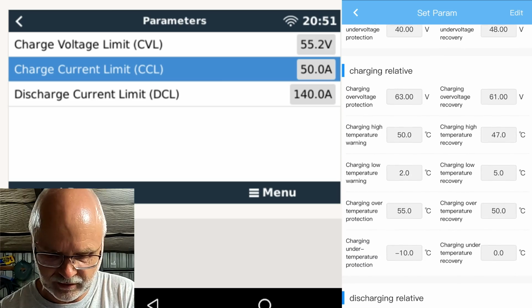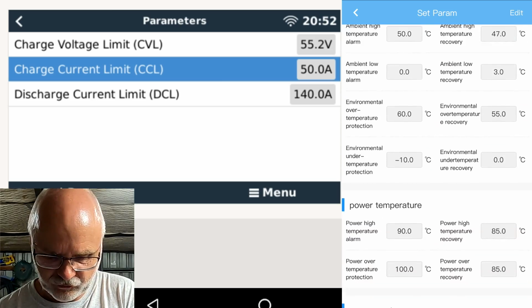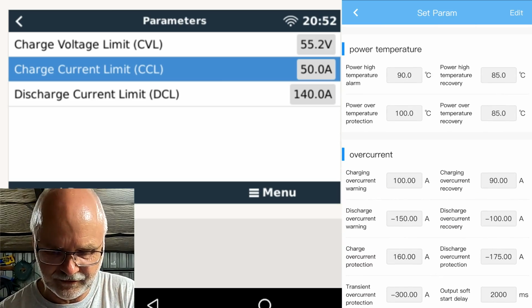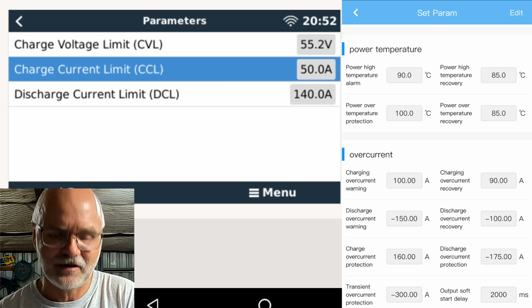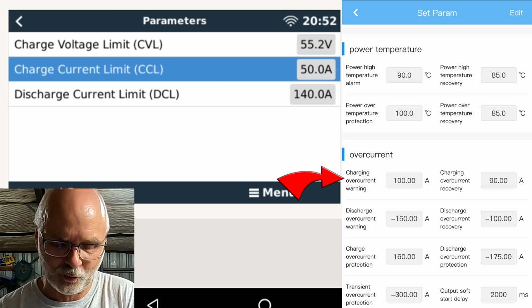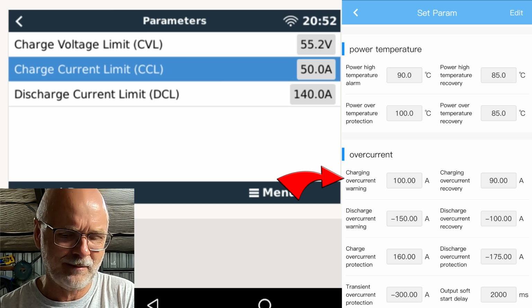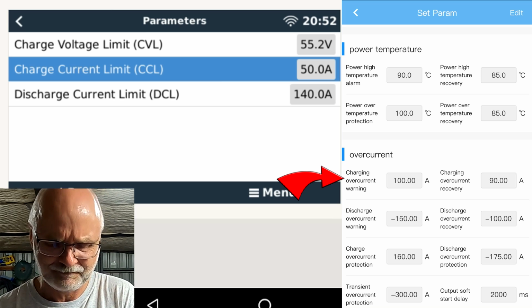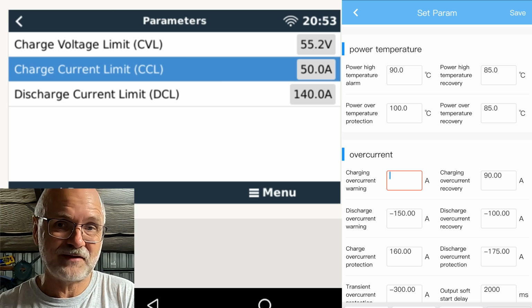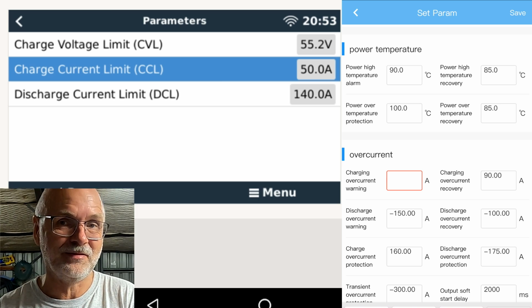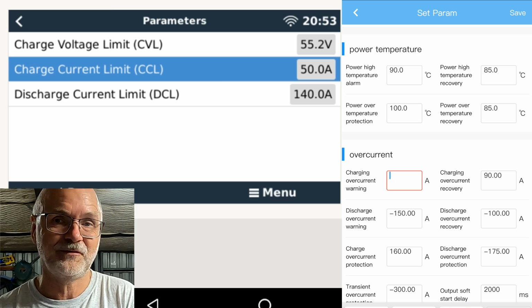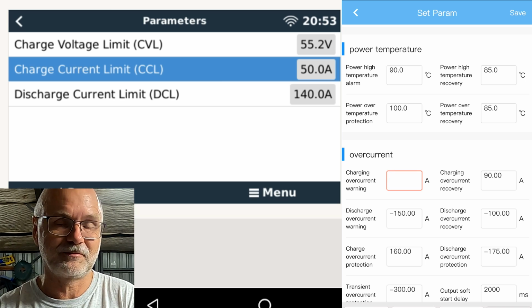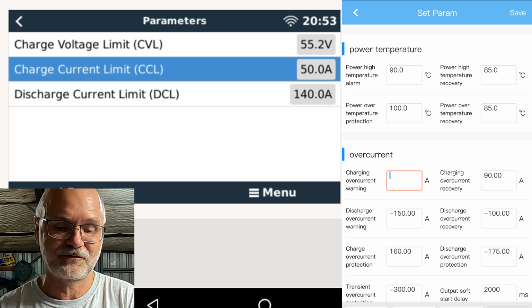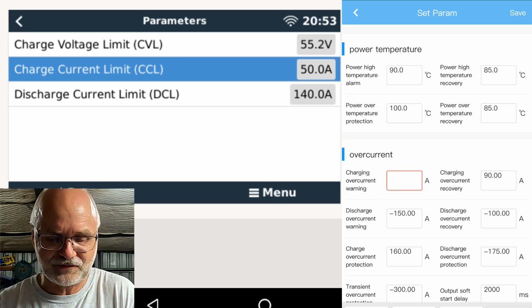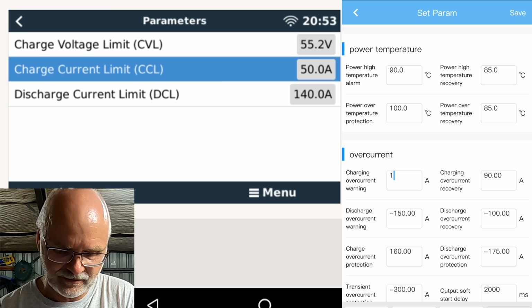And to find this parameter, we have to go all the way down to overcurrent. And the important setting here is the charging overcurrent warning. You can see it sits at 100 amps. So why does it show only 50 amps there? I found out that it is exactly half of what we are setting in the BMS. So if you set 100 amps, the charge current limit will be 50 amps. If you set 200 amps in the BMS, your charge current will be 100 amps. Why that is, I don't know.